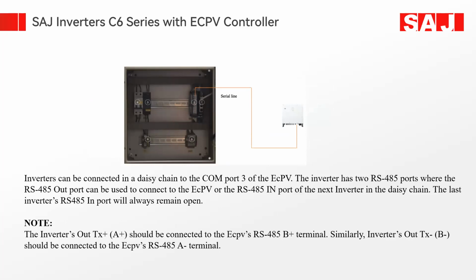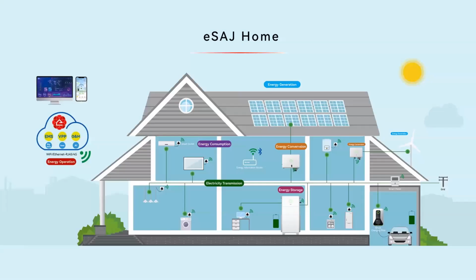The inverter RS485 out B positive should be connected to the ECPV RS485 B plus terminal. Similarly, the inverter RS485 out A negative should be connected to the ECPV RS485 A negative terminal. These are the connections to synchronize the C6 inverter with the third-party controllers.